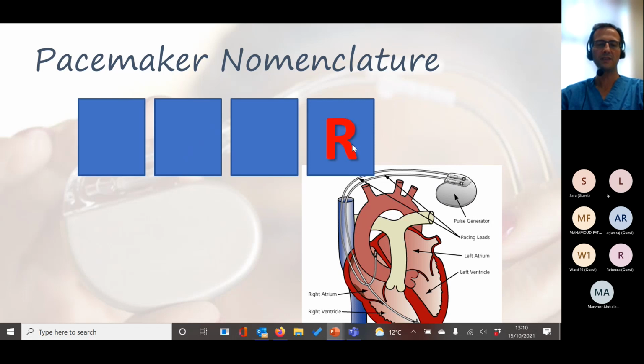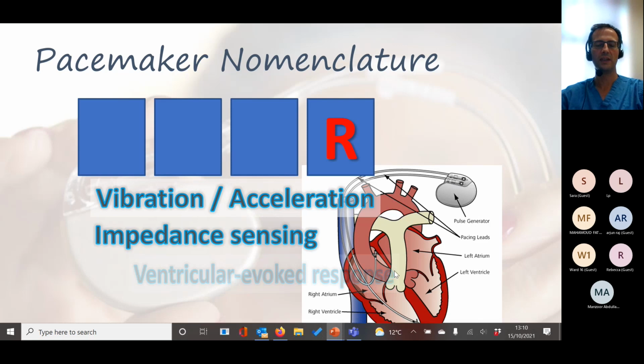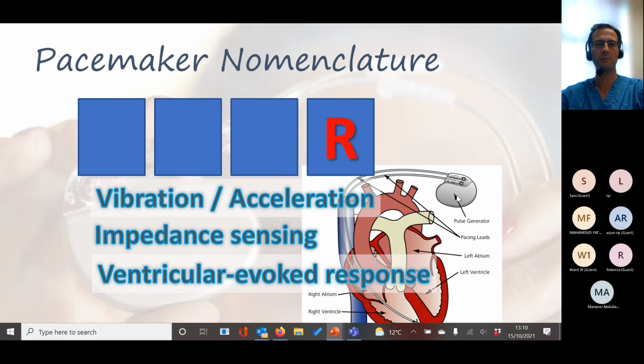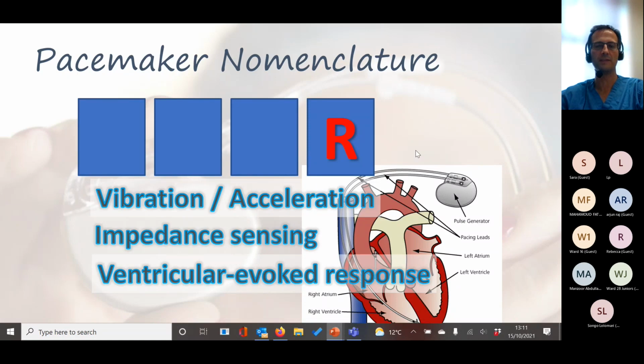And then the last letter is an optional letter, and it's an R for variable rate or rate responsive, and it can use vibration. So if you shake a pacemaker around and then put it in, the patient gets a tachycardia because the pacemaker has been shaken around before you put it in. Sometimes we do that inadvertently. It very rapidly settles down. It can also do things like sense how fast a patient's breathing by looking at thoracic impedance. So pacemakers can do various clever things to work out how fast the heart needs to go if they can't rely on the natural pacemaker, either because you've got sinus node disease or you might be in atrial fibrillation, say.